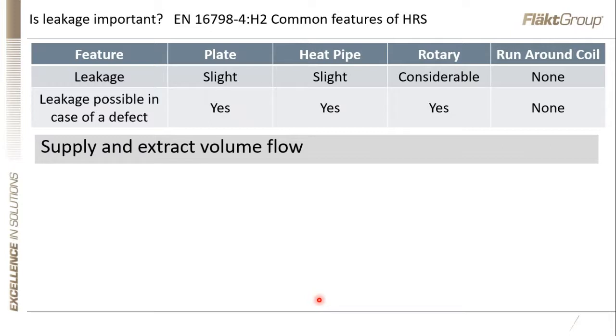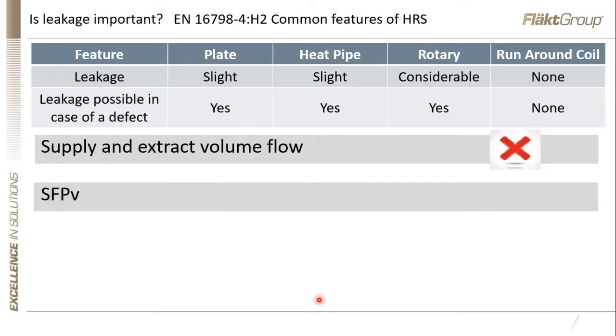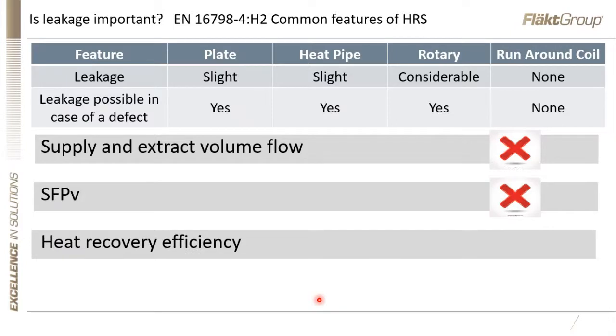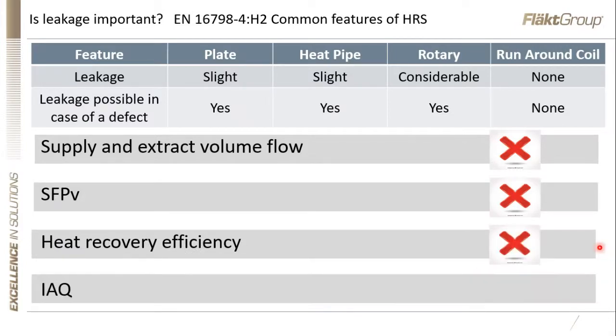So what effect could that have on the overall system and what we're trying to achieve with an air handling unit? The supply and extract volume flow could actually be wrong if there's excess leakage in the air handling unit. The SFPV could be wrong. The heat recovery efficiency could also be wrong. And most importantly for the subject of tonight, the indoor air quality might be poor as a result of leakages in the air handling unit. And that, of course, could contribute to some COVID material being recirculated by the air handling unit back into the occupied space.